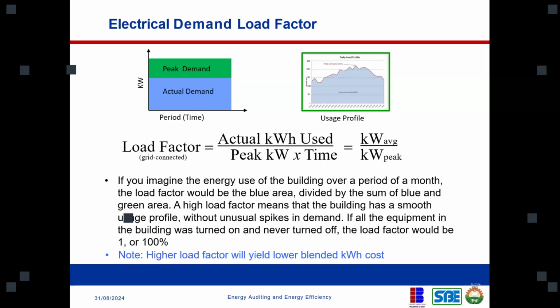Now, if you see that kind of situation, you can then advise, anytime you need to use this equipment, please shut down every other equipment so you don't create unnecessary demand. Now, these are energy management strategies, how to actually reduce your demand. But for us to understand this, that's why I have put this electrical demand load factor here, just for us to understand how demand factor affects our energy bills and sizing of our equipment.